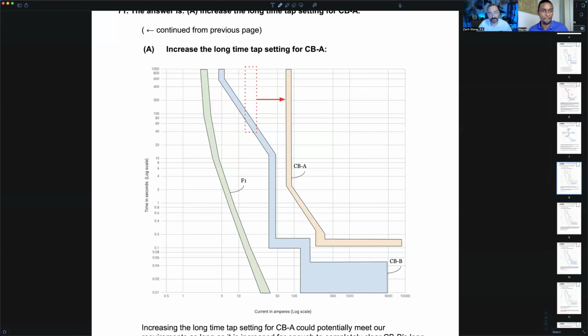Here was the answer: increasing the long time tap. Same thing as your secondary pickup. Here's the new pickup on the horizontal axis, right where that leading edge starts. Previously it was somewhere over here. So increasing the tap setting is like dragging just that vertical portion of long time all the way to the right, specifically for the long time tap setting.